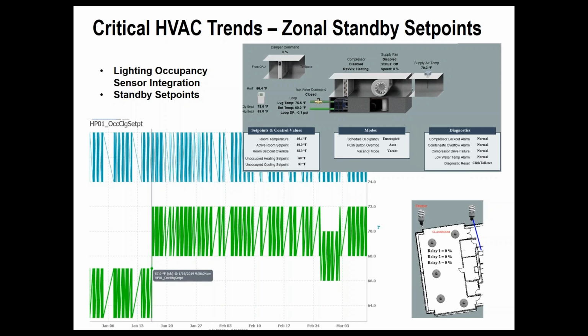Again, a little bit of a confusing graph, but I'll try to explain it here. We have standby temperatures for all the zones. There's a level of integration between the lighting control occupancy sensors and the temperature set point control. So we don't just have occupied space temperature set points and unoccupied space temperature set points. We actually also have standby set points. And this wasn't an HVAC-only control method. We actually had integration with the lighting control system. Unless I sit there and watch where people are going and how the occupancy sensors are working, I can't tell that this sawtooth we're seeing here is 100% accurate. But what I can see is that on a regular basis we are going back and forth between the occupied space temperature set points and the standby space temperature set points. That gave me a level of confidence that things were working pretty decently here.